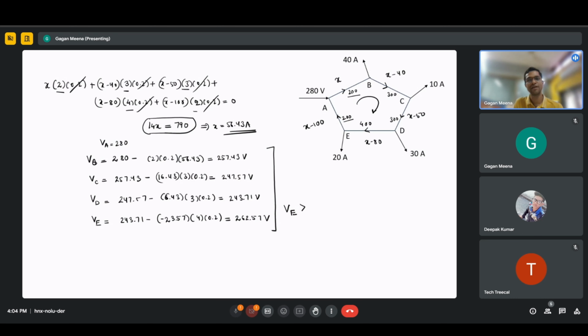But at point B, load is drawing 40 amperes. At point E, load is drawing 20 amperes. That is why, because current drawn here is less, voltage drop here is less. Both are at the same distance from the substation, but here drop is less. That's why voltage here is higher.